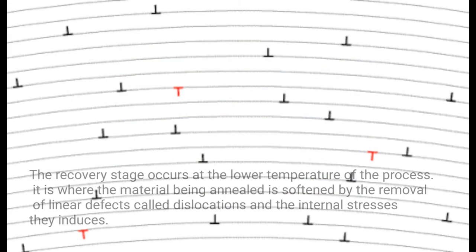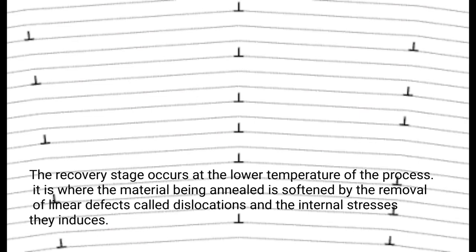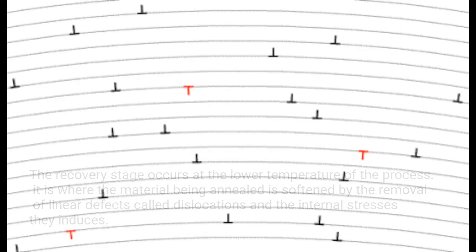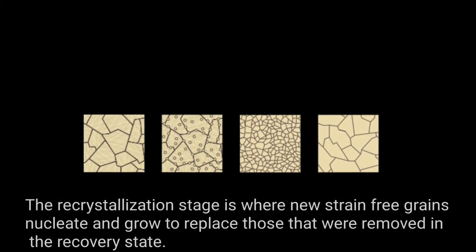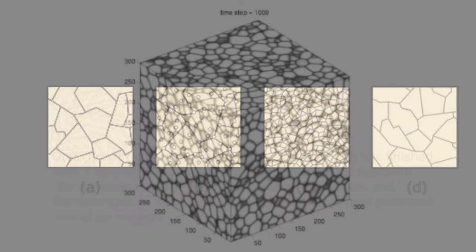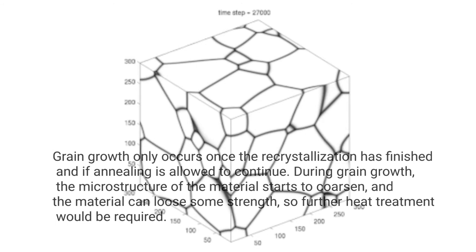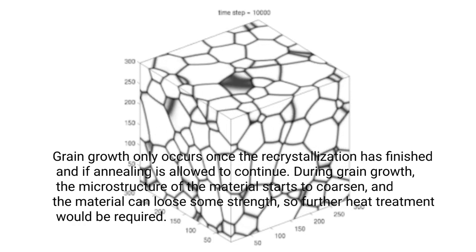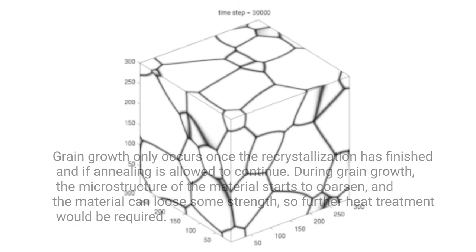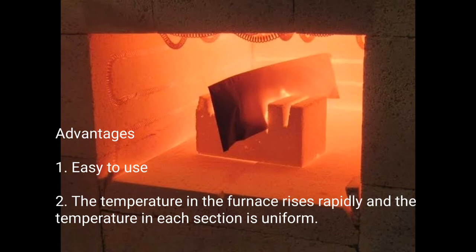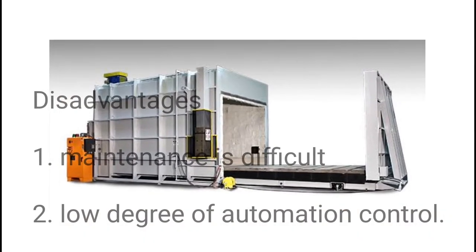There are three stages in an annealing furnace: recovery, recrystallization, and grain growth. The recovery stage occurs at lower temperatures, where the material is softened by the removal of linear defects called dislocations. The recrystallization stage is where new strain-free grains nucleate and grow to replace those removed in recovery. Grain growth only occurs once recrystallization has finished; if allowed to continue, the microstructure coarsens and the material can lose some strength. Advantages: easy to use; temperature rises rapidly and is uniform in each section. Disadvantages: maintenance is difficult; low degree of automation control.